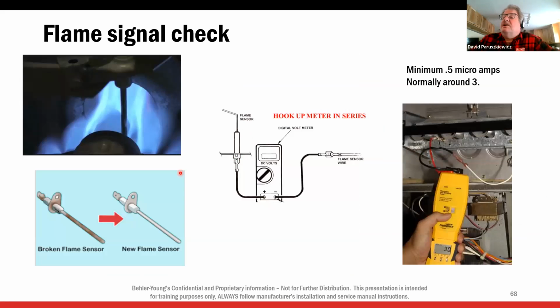All right. The flame rod, and again, I sound like a broken record here, but the flame rod is not a thermocouple. Heat has nothing to do with it. It's a conductor. It's a contact, if you will. So the flame rod is a piece of steel. You can clean it as long as the ceramic is not cracked. The flame rod is fine.